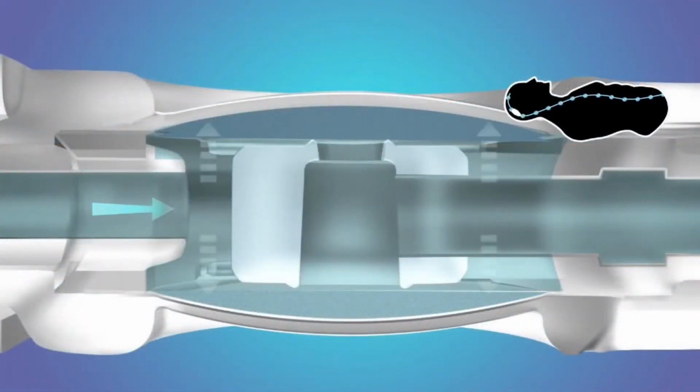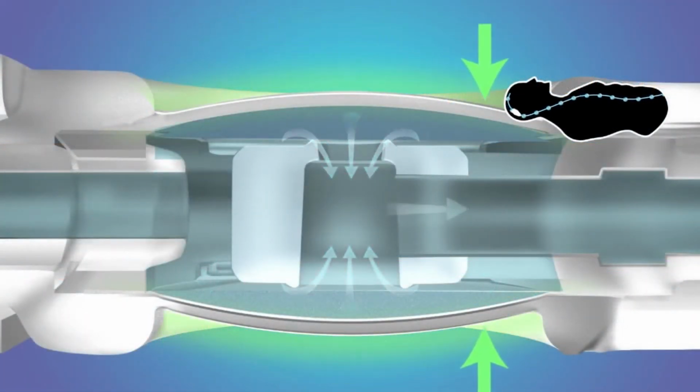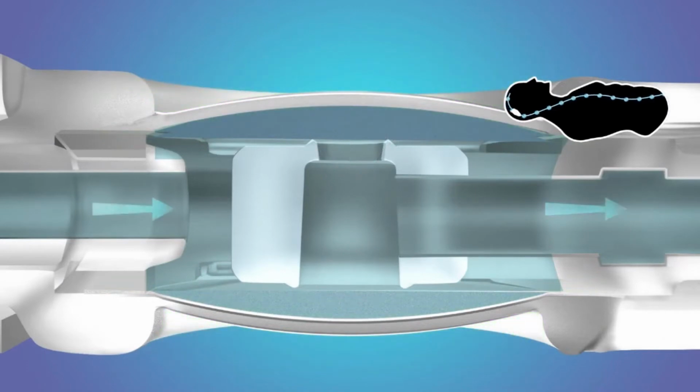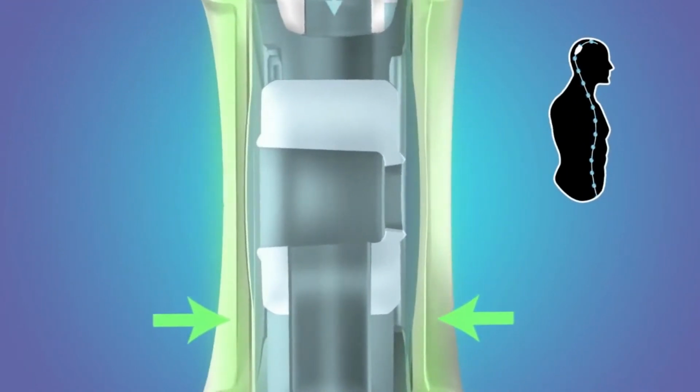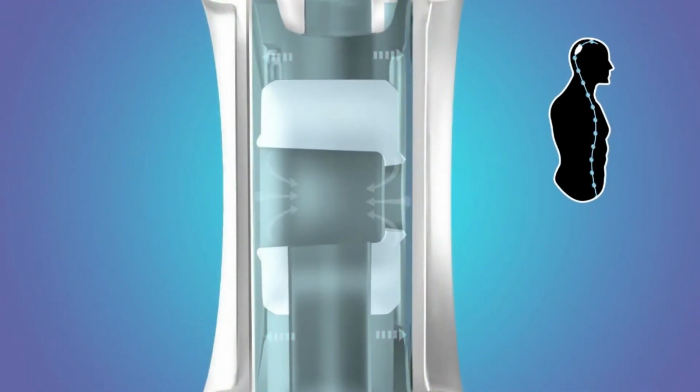When the patient is in the supine position, the membranes on either side of the delta chamber are relaxed or open, allowing for CSF flow. When the patient stands up, the negative pressure pulls the membranes closed, reducing the flow of CSF.